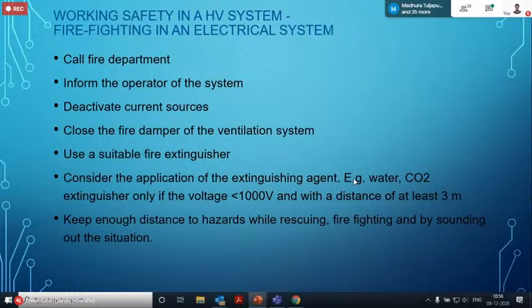Inform the operator of the systems, deactivate the current sources, close the fire damper of the ventilation systems, use suitable fire extinguishers, and consider the application of existing extinguishing agents like water or CO2 extinguishers only if the voltage is less than 1000 volts, with a distance of at least 3 meters. Safe working distance is 3 meters.